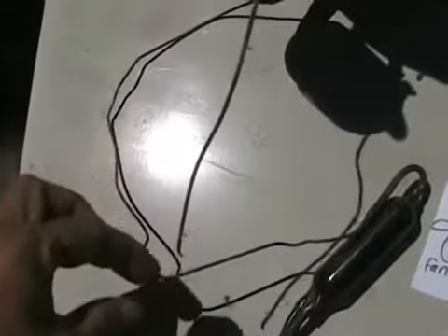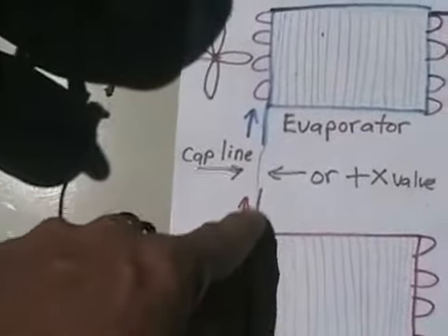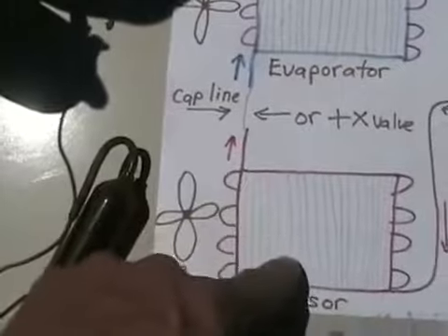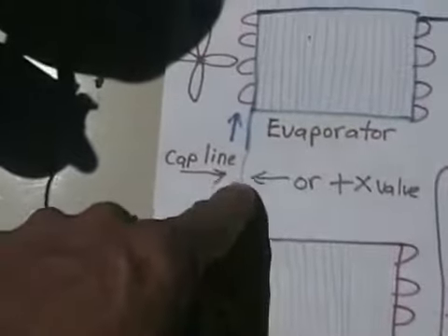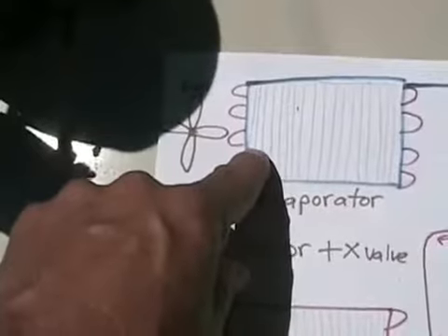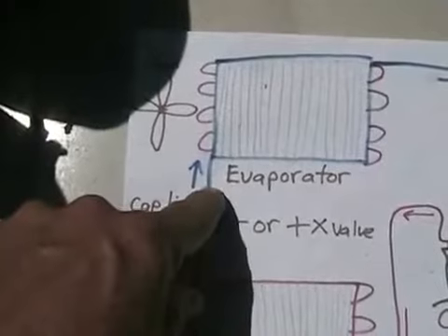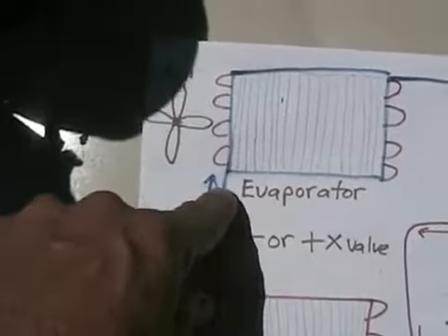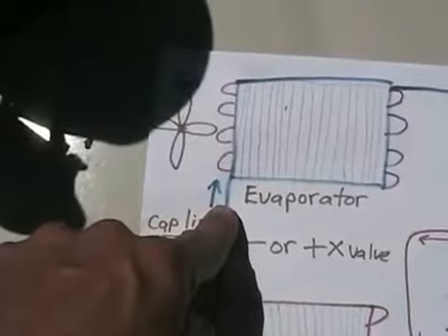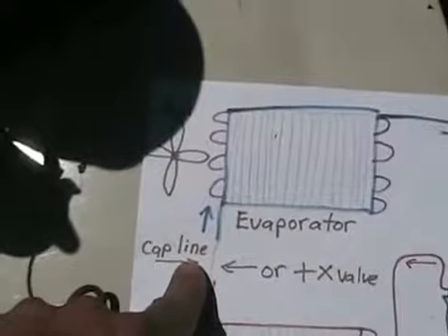The reason you have this long, skinny, restricting tube that forces the Freon through very difficultly is so that it can create back pressure, so we maintain liquid Freon on the condensing coil. By the time the Freon goes the distance of that tube and gets to the evaporator, it is all the largest diameter tubes on the air conditioner, much larger than this tube. This gives the liquid Freon some place to want to expand, and when a liquid turns to a gas, that's called evaporating, and it makes itself colder.